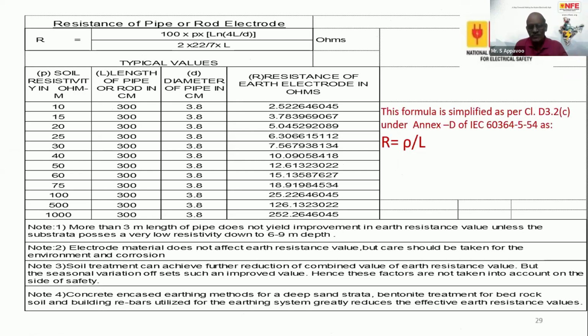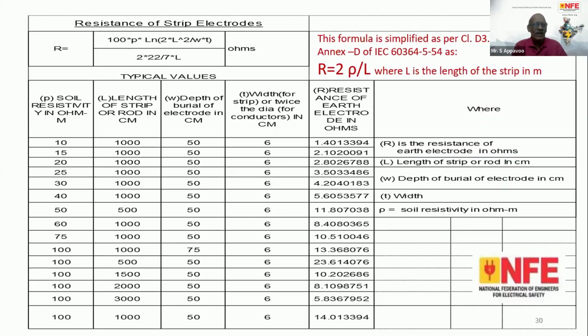For example, a pipe electrode, it all depends upon the soil resistivity. A pipe electrode at a soil resistivity of 100 ohm meter, for example 3 meters long, can give you 25 ohms. But you can achieve the same with a flat strip electrode for the same 100 ohm meter soil resistivity, but the length should be double that. So the same effect can be achieved, and you can achieve the potential grading to minimize the touch potential.